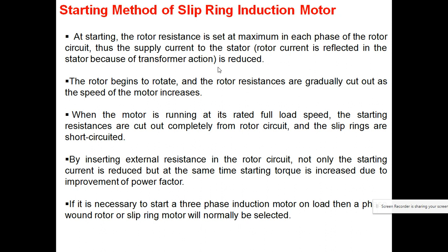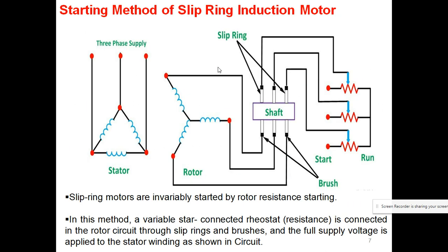Is it okay? Once the rotor begins to rotate, the rotor resistance is gradually cut out as the speed of the motor increases. So what we are basically doing is putting the rheostat at the high position, and in that condition the rotor current will decrease, and we see that reflected in the stator current due to transformer action. That is our purpose: to decrease the starting current using the stator.